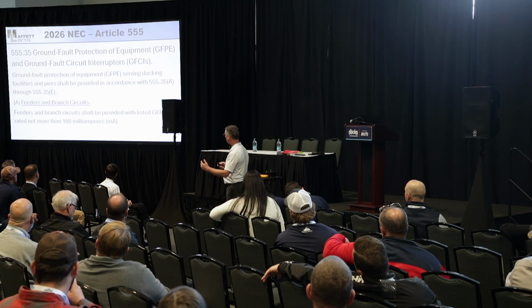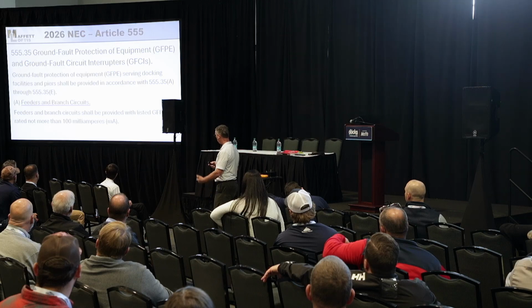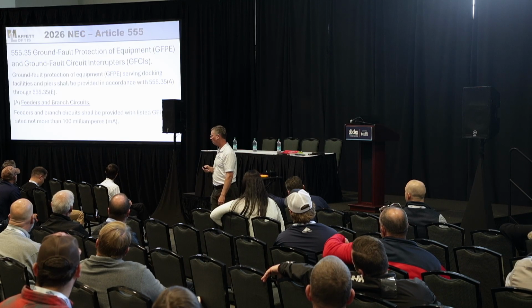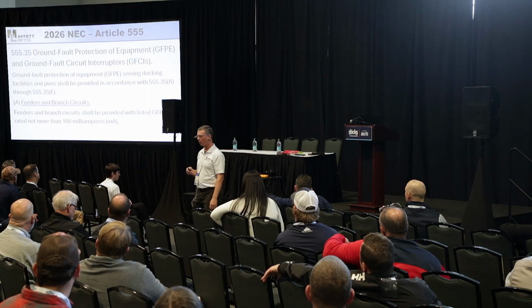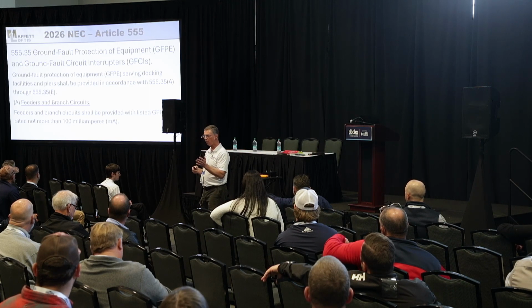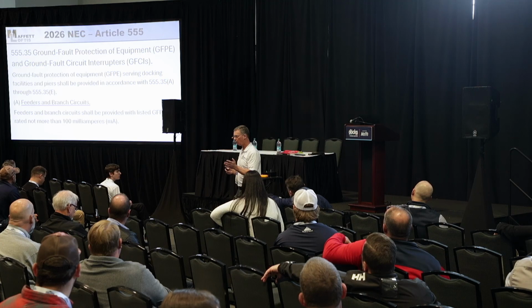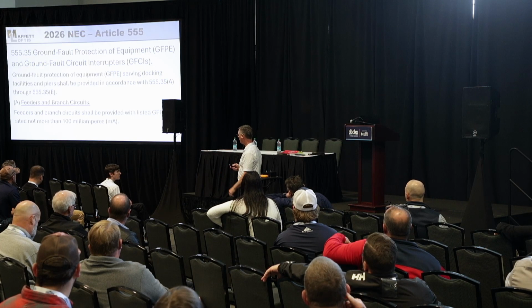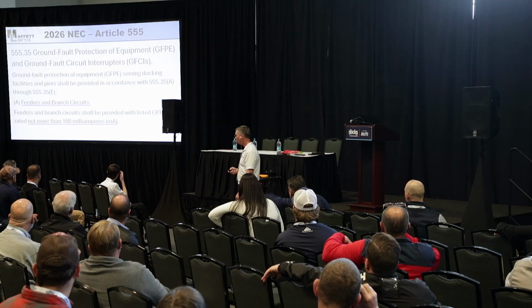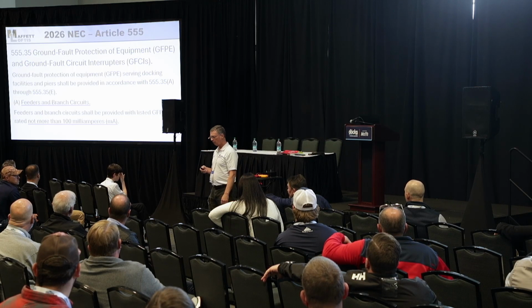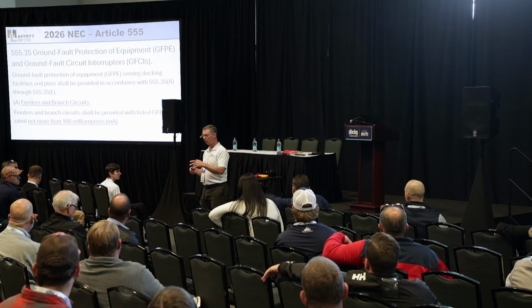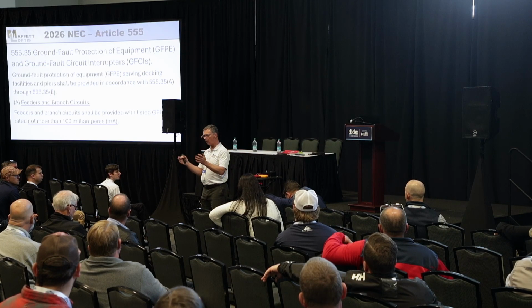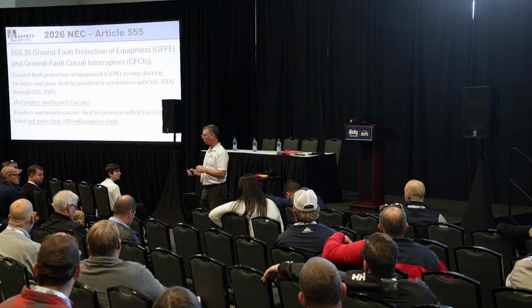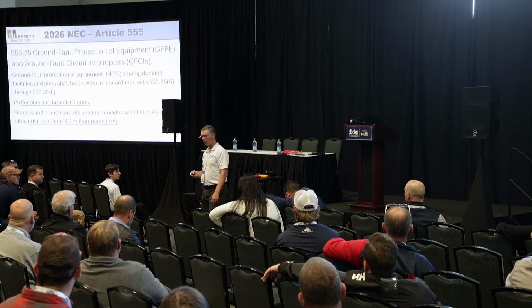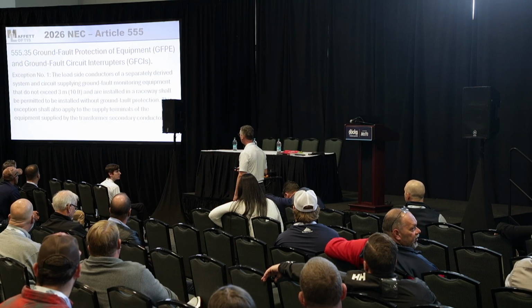This is really not new, but it's worded a little bit differently, about branch circuits and feeders. We had a little bit of a hole in the ground fault protection. There were some circuits that were not required under the 2023 code to have 100 milliamp GFPE. So we kind of fixed that by saying the branch circuits, because you could have some lighting on a little party deck or a gazebo out on your marina, and that lighting circuit was not required under 2023 to have GFPE on it. And this language fixes that.